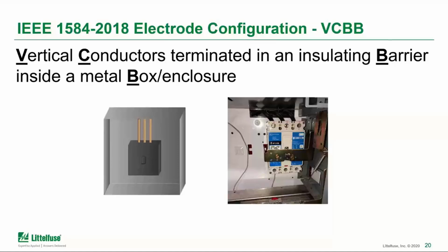The next configuration, VCBB, has vertical conductors into a barrier in a box. Again, in the photo example on the right, you can see the conductors terminated onto a piece of equipment. So it's terminated onto a barrier. They're not just open, and again, it's in an overall enclosure. In this case, when you have arcing occurring at that barrier, the energy cannot go into the barrier, so it's reflected outwards off that barrier. So that again has an effect on what energy would be experienced by somebody standing in front.